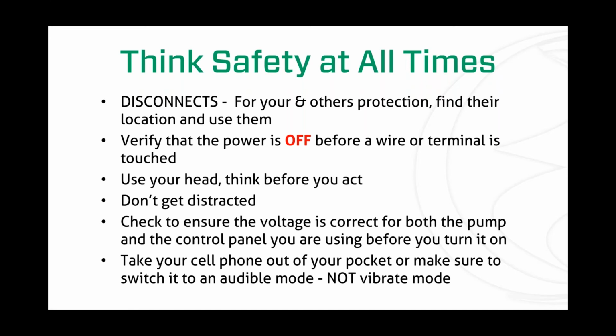Again, check the voltage. This is not only to make sure it's off, like I previously mentioned, but also to verify the voltage is correct for both your panel and your pumps. Sometimes you have different voltages for the panel and the pumps. If you have the wrong voltage going to your control panel, you can fry or burn up components inside it in just the blink of an eye. It can be a very expensive learning lesson and, of course, not to mention dangerous.